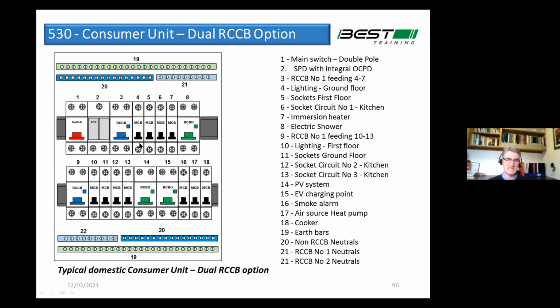all the lighting circuits in a house now must be protected by an RCD. Okay, so you can't put everything on one RCD, or a trip on a faulty toaster, faulty kettle or something could knock everything out in your house, all your sockets and all your lights. That would not be on. It wouldn't be compliant with chapter 3, which talks about divisions of circuits for safety, etc.